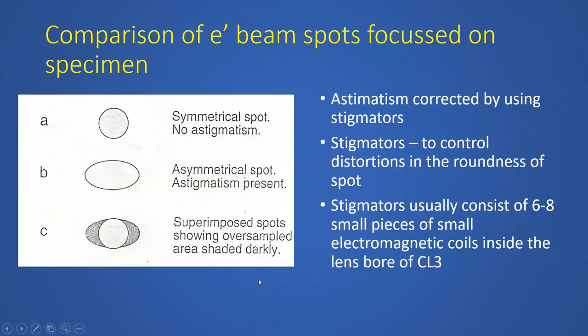So, a comparison of electron beam spots focused on the specimen. This is the kind of spot that you would like to have. It's a symmetrical spot. There is no astigmatism. Astigmatism is an aberration that results from unequal magnetic fields. You can compensate for this using stigmators, which are basically 6 to 8 small pieces of electromagnetic coils placed inside the bore of the condenser lens 3. So this is called a stigmator.